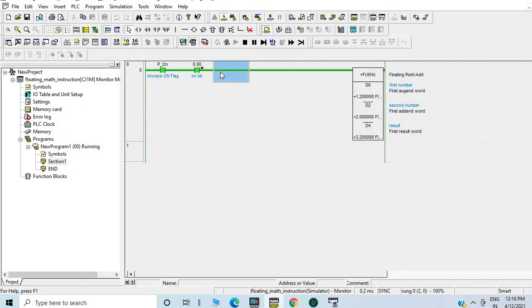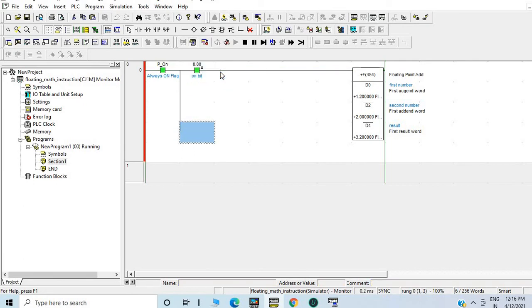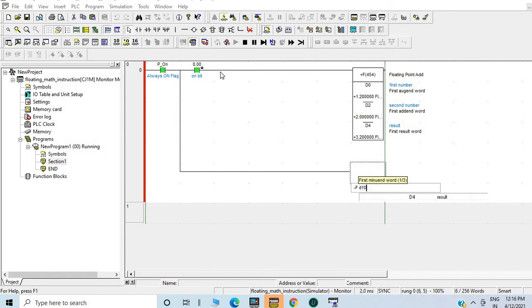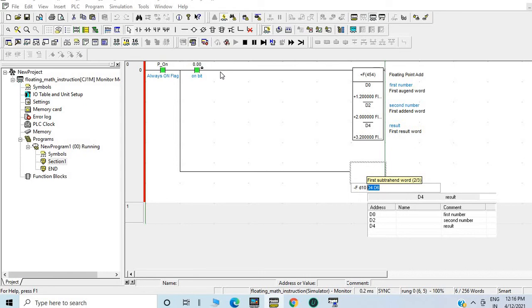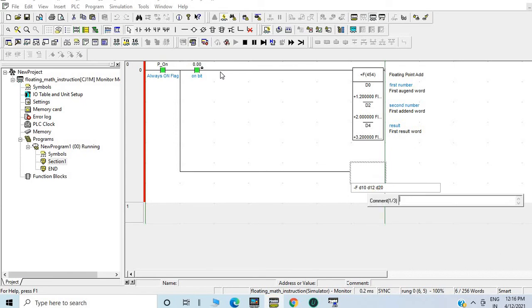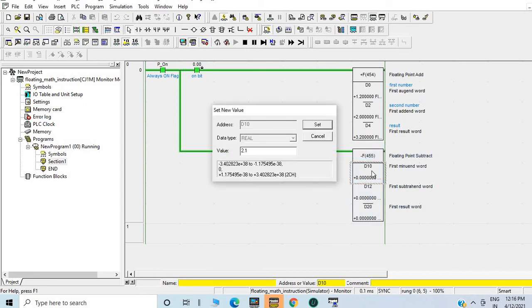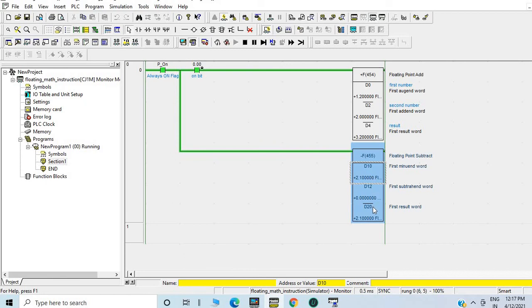Now we will go to floating point subtraction. I am giving a new instruction — minus floating point F. First number D10, second one will be D12, and third one will be D20 data register. I need to send the changes — Shift+Ctrl. Sending the changes now. You can see D10 value is 0. Suppose I am putting 2.1 in D10 — so 2.1 minus 0 will be 2.1.